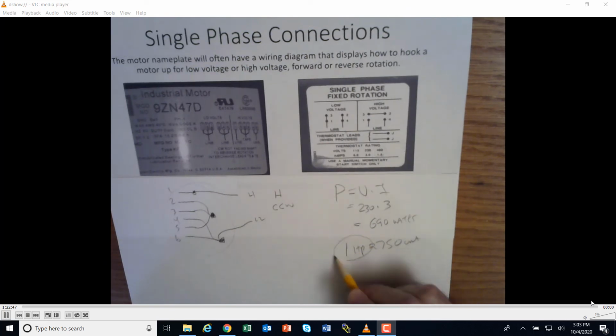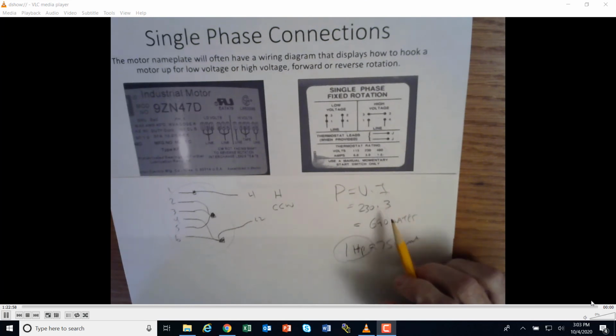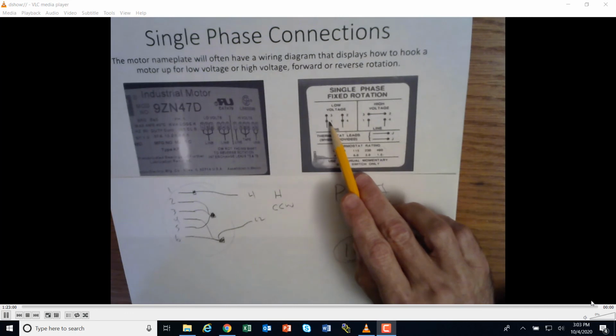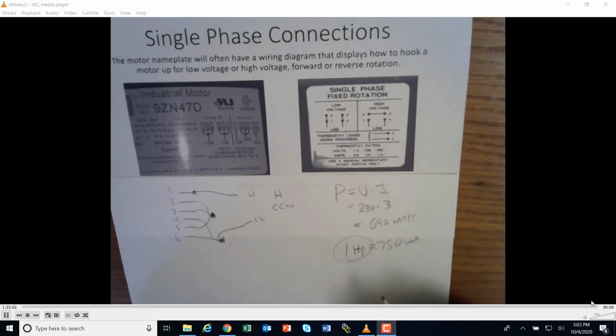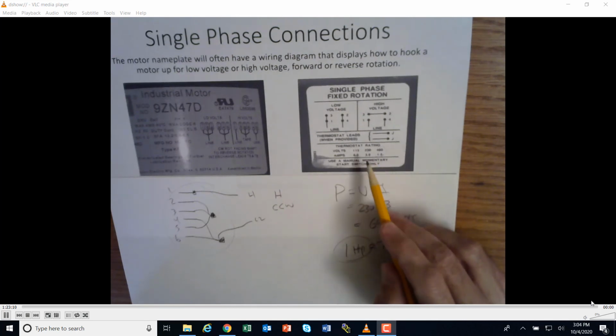Okay. And so with a 1 horsepower motor, you could then go and size your starter and overload. I'm sorry, it's a single phase. You would size your contactor to turn on your lines, whether you had it wired up as low voltage or high voltage, and you know the electrical characteristics based on the fact that it's about a 1 horsepower motor drawing this many volts and this many amps.